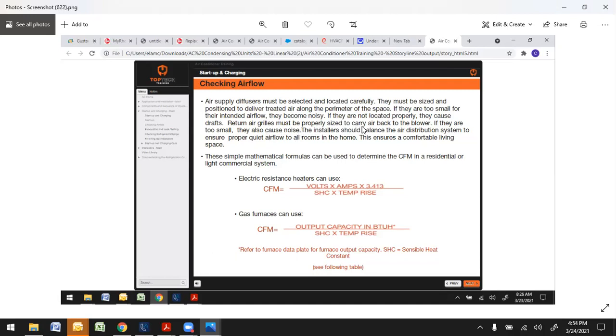Return air grills must be properly sized to carry air back to the blower. This is a big one. If they're too small, they will also cause noise. They'll make a humming or a high-pitched whistle if they're too small. So it is important that the installers or the salespeople understand what the duct system is. In a quick glance, you can see what it looks like and what it should be able to handle, to ensure you install the proper furnace, airflow, and AC system.